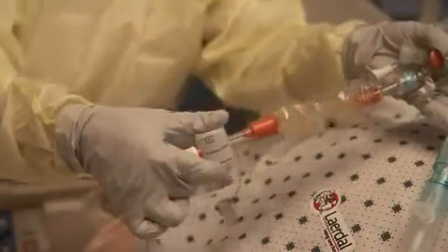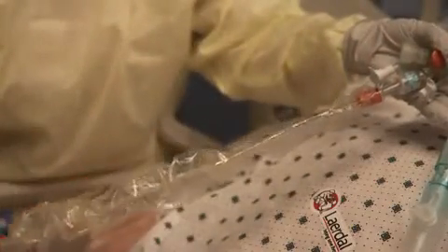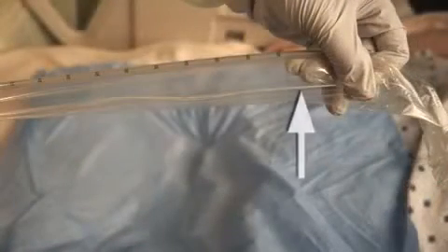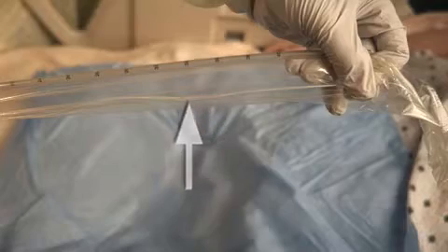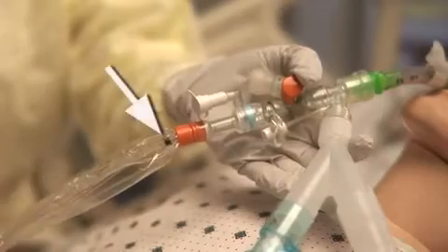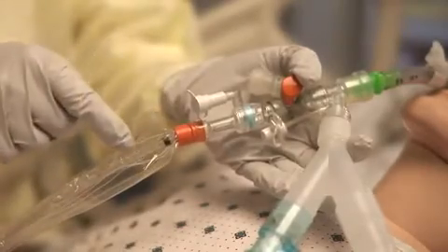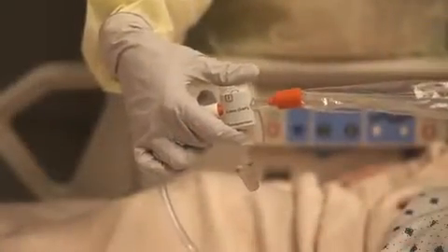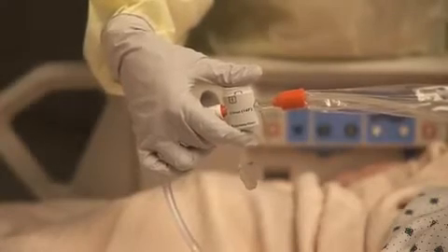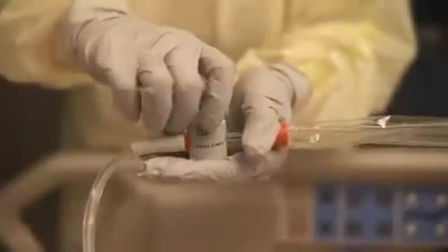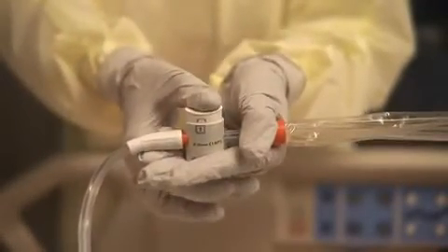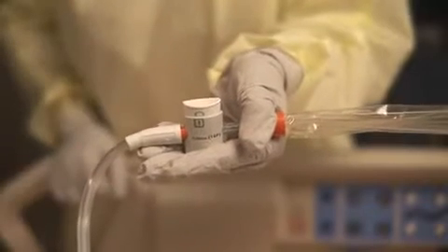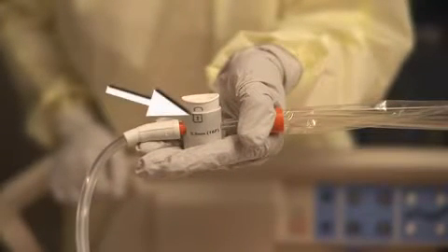Depress and hold the thumb control valve, then gently withdraw the catheter. The tethered sleeve, which provides a stop when retracting the catheter, therefore prevents over-retraction that leads to the inflation of the sleeve. Stop withdrawal when the black marking ring is visible inside the sleeve. Release the thumb control valve and repeat the previous steps as necessary. Lock the thumb control valve when not suctioning to prevent inadvertent or accidental activation. The lock graphic provides a clear indication that the suctioning thumb valve cannot be depressed.